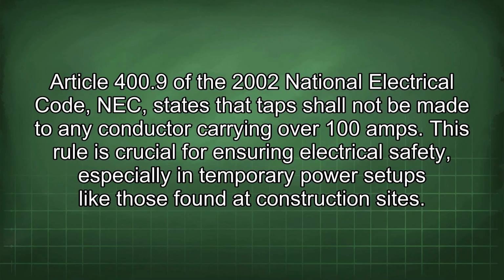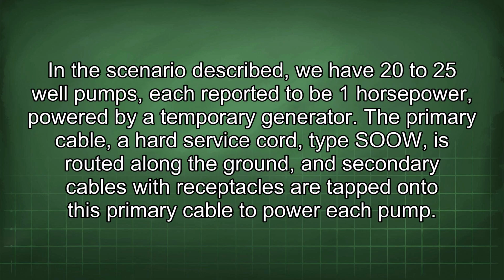Article 400.9 of the 2002 National Electrical Code, NEC, states that taps shall not be made to any conductor carrying over 100 amps. This rule is crucial for ensuring electrical safety, especially in temporary power setups like those found at construction sites. In the scenario described, we have 20 to 25 well pumps, each reported to be 1 horsepower, powered by a temporary generator. The primary cable, a hard service cord, type SOOW, is routed along the ground, and secondary cables with receptacles are tapped onto this primary cable to power each pump.